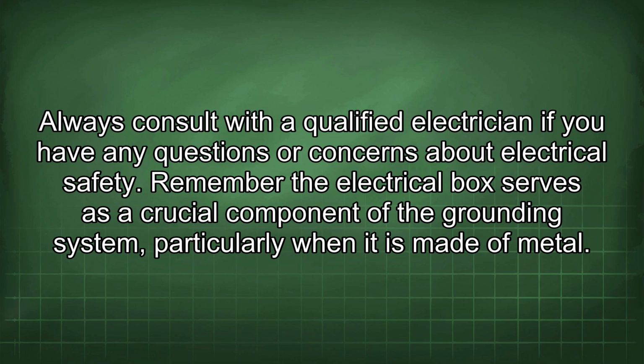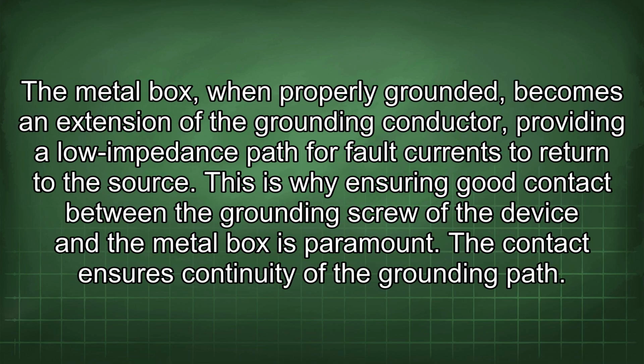Remember, the electrical box serves as a crucial component of the grounding system, particularly when it is made of metal. The metal box, when properly grounded, becomes an extension of the grounding conductor, providing a low impedance path for fault currents to return to the source. This is why ensuring good contact between the grounding screw of the device and the metal box is paramount. Contact ensures continuity of the grounding path.